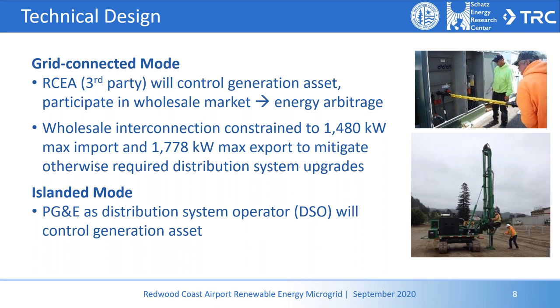When we go into island mode, however, PG&E, as the distribution system operator, is responsible for serving their customers safely, reliably, and with proper quality. They have control over when we go into island mode, which will only be in emergency situations where there's a grid outage, and they also will have control of the generator in island mode. Actually, the generator in island mode will be automatically controlled by the software, forming the grid and meeting the load. So there's nothing really PG&E is going to be doing with it, but from a responsibility standpoint, they are in control.